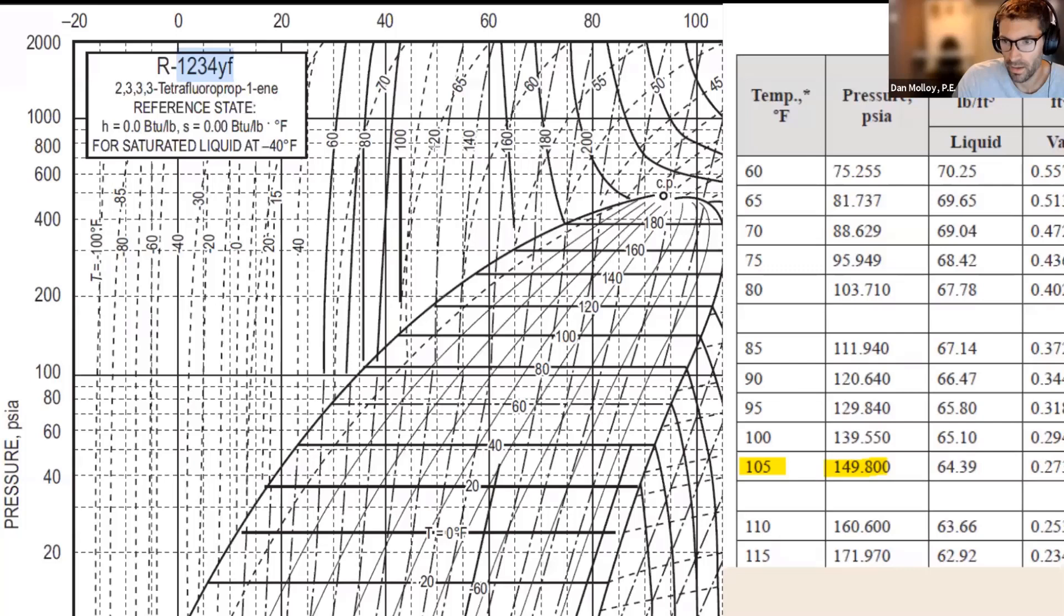So if you are doing 20 degrees superheat, let's just say for example you're starting from, let's say, the temperature of the evaporator is 40 degrees, then you're going to add 20 degrees of superheat. You're going to go horizontally until you hit the 60 degree temperature line.